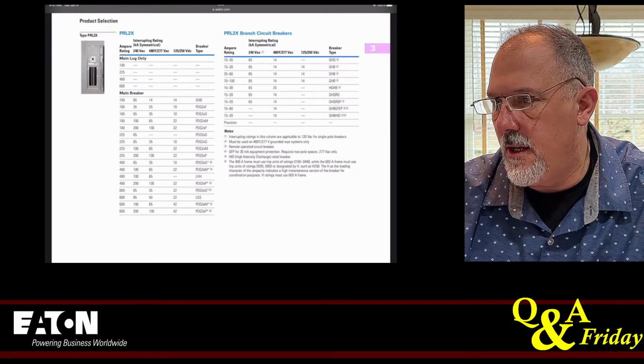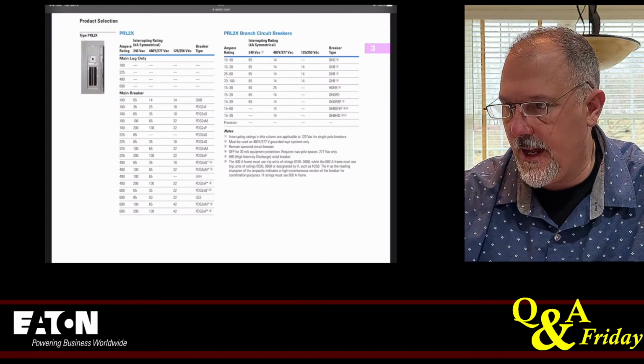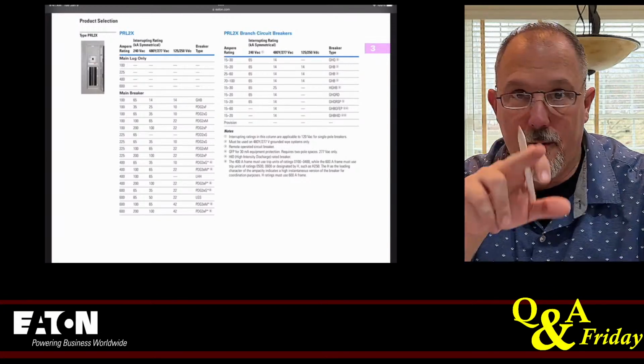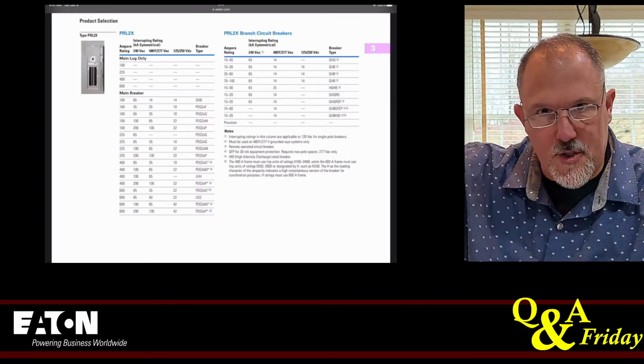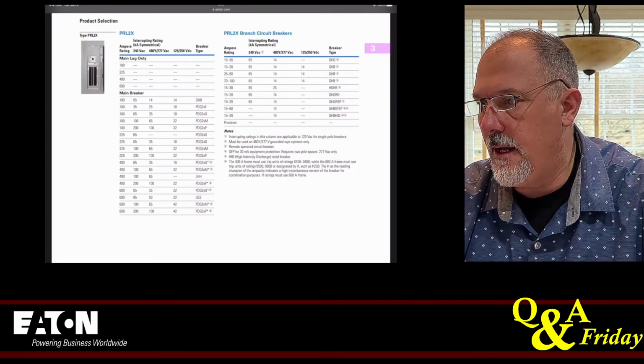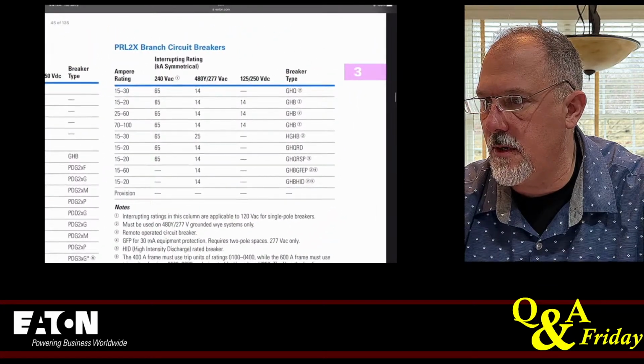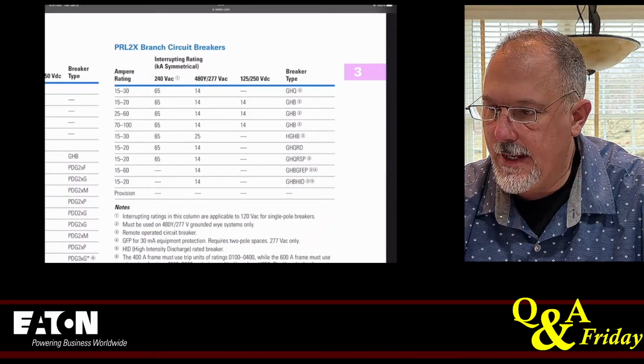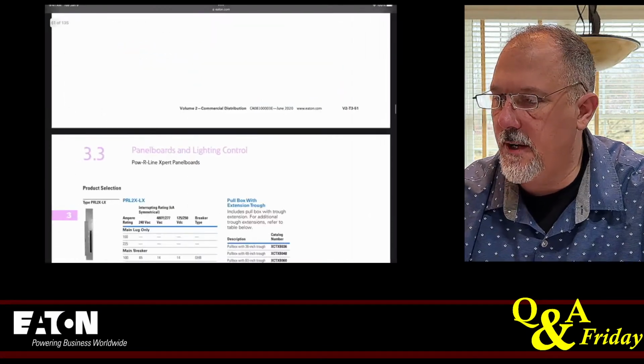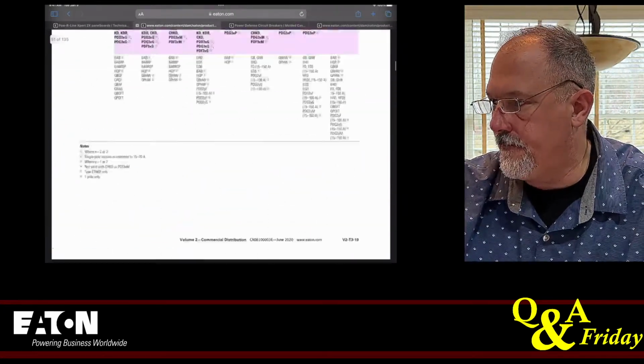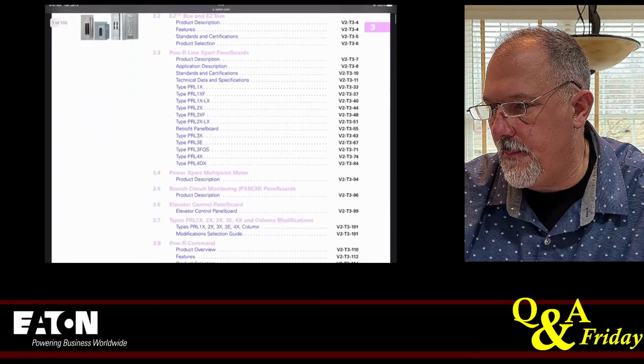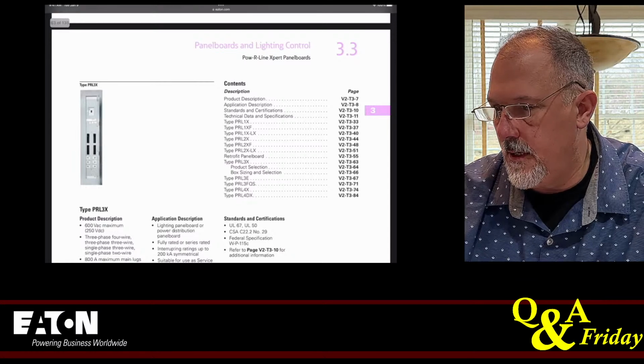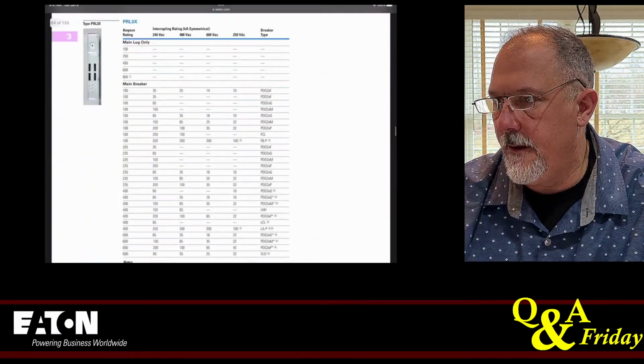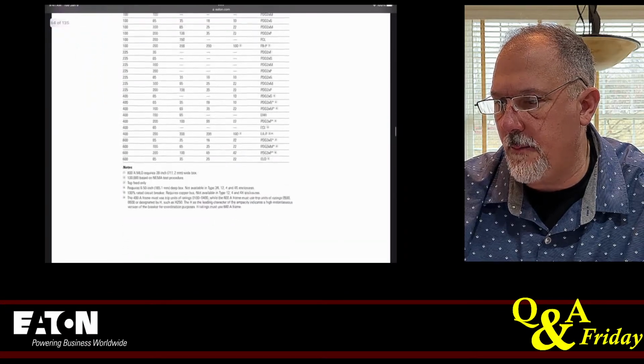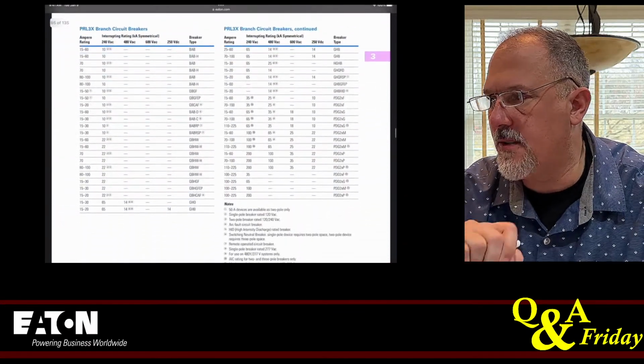So a Powerline 2X is 480, 277, and I have 125 amp. Remember, I have a 125 amp feeder going to the transformer. So my upstream panel board cannot be Powerline 2X because look, this is your branch circuit breakers, I can't go higher than 100 amps. So for an upstream panel board, I'm not going to be in a Powerline 2X. What am I going to be in? I am going to probably be in a Powerline, let's try a 3X. Powerline 3X. There is my main lug only. There's my main breakers. Here are my branch breakers.